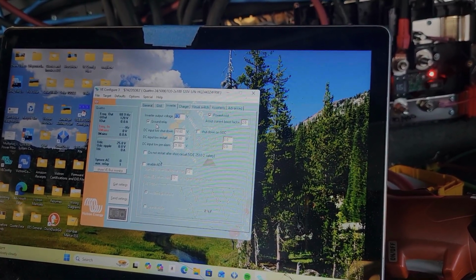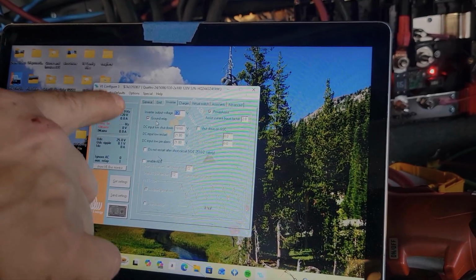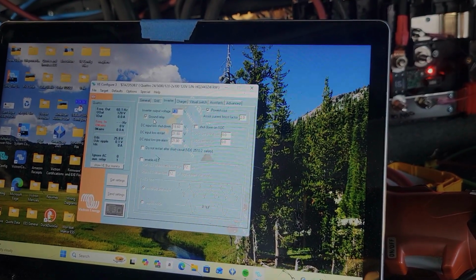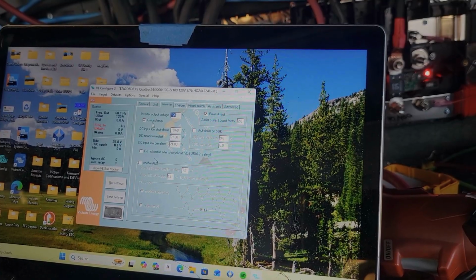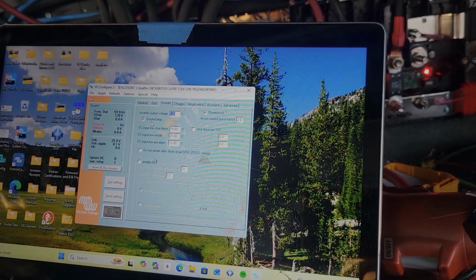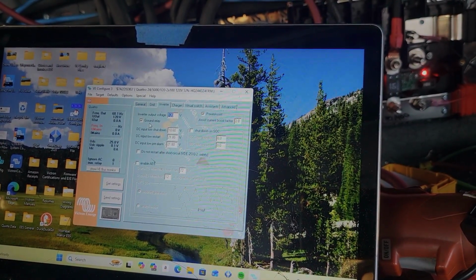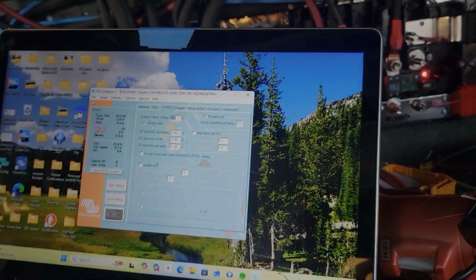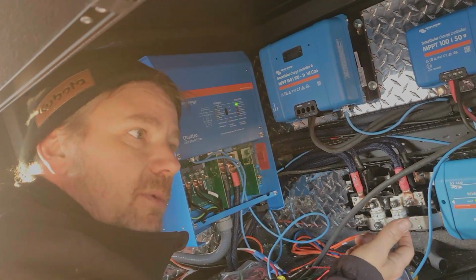If the authority having jurisdiction says that, it's as simple for us as just disabling that function. And now we've got control of it at the panel. But in a mobile application, it's important to have that neutral and ground bond, even when you are in inverter mode.